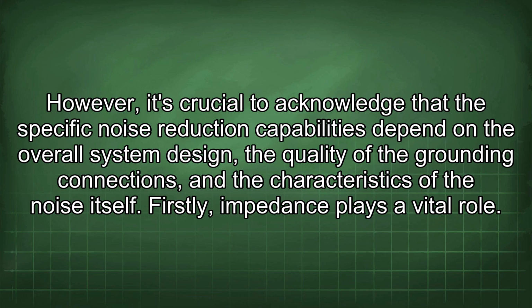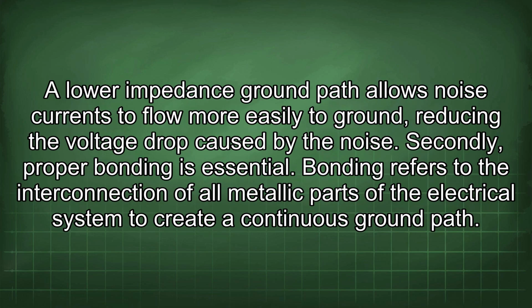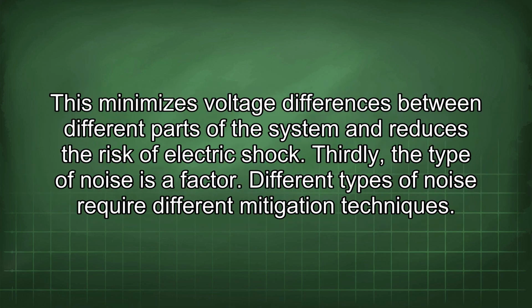Firstly, impedance plays a vital role. A lower impedance ground path allows noise currents to flow more easily to ground, reducing the voltage drop caused by the noise. Secondly, proper bonding is essential. Bonding refers to the interconnection of all metallic parts of the electrical system to create a continuous ground path. This minimizes voltage differences between different parts of the system and reduces the risk of electric shock.